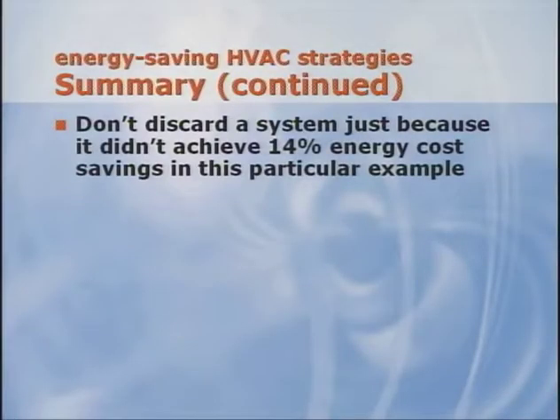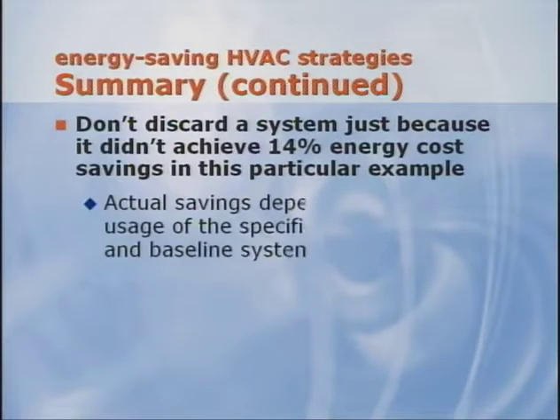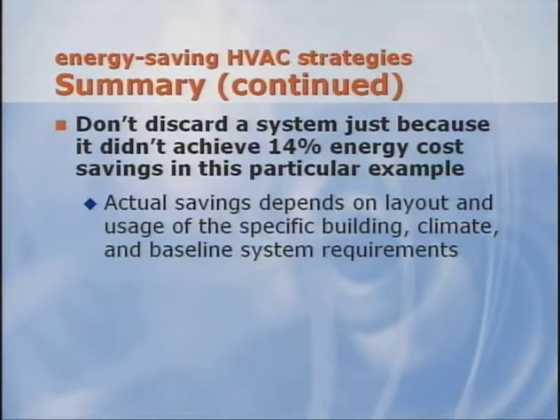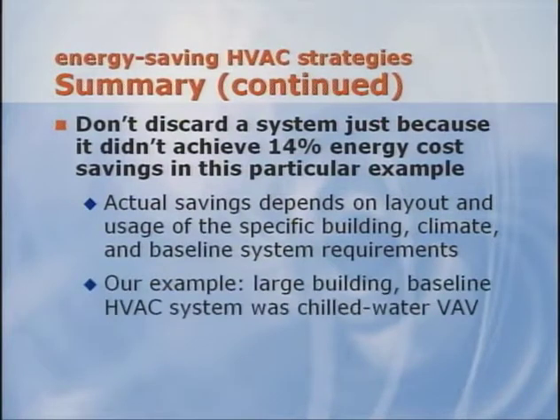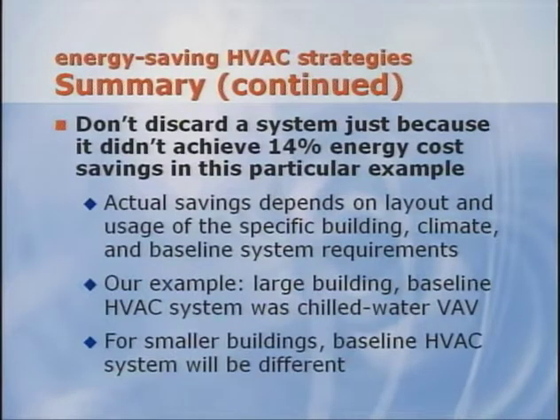Be careful not to discard any of the system choices investigated in this study just because it didn't achieve at least 14% energy cost savings in this particular example. Actual savings depends on the layout and usage of the specific building, the climate, and the baseline system requirements. Remember, our example was a fairly large building, so the baseline was equipped with a chilled water VAV system. For smaller buildings, the baseline system will be different.